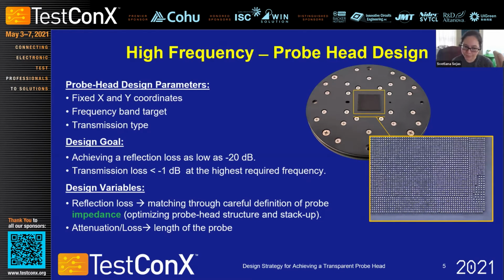But how can we optimize it? Well, the reflection loss is the impedance, and we can optimize the impedance through the correct selection of the probes and the right design of the stack up of the probe head. And that will immediately improve the transmission loss. And now the transmission loss only depends on the loss of the probe, which can be modified through the length of the probe.